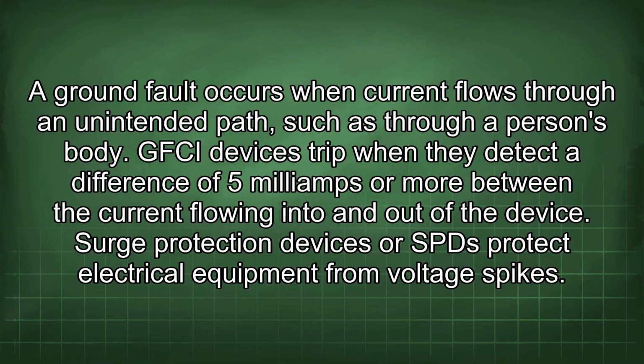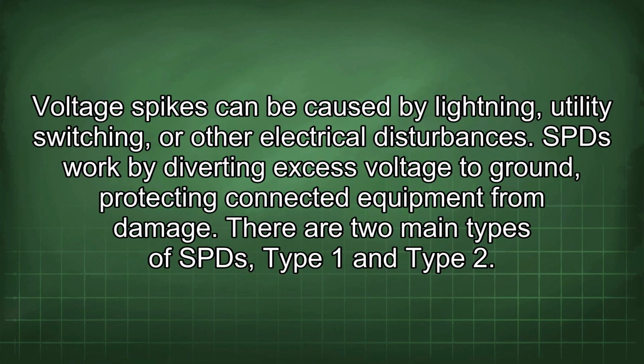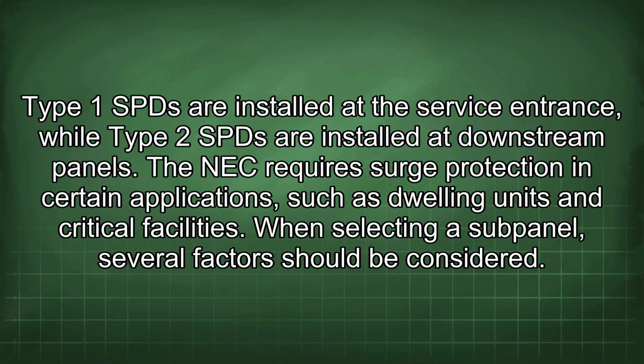Surge protection devices, or SPD, protect electrical equipment from voltage spikes. Voltage spikes can be caused by lightning, utility switching, or other electrical disturbances. SPD work by diverting excess voltage to ground, protecting connected equipment from damage. There are two main types of SPD, Type 1 and Type 2. Type 1 SPD are installed at the service entrance, while Type 2 SPD are installed at downstream panels. The NEC requires surge protection in certain applications, such as dwelling units and critical facilities.